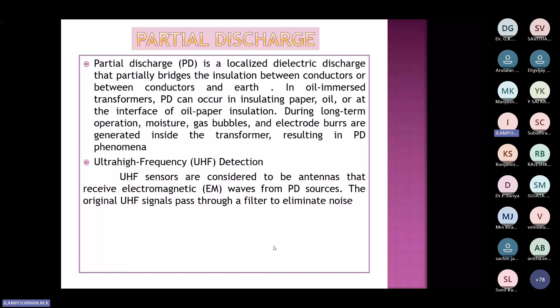If you have only one source of partial discharge, no problem, you can detect it perfectly. But God does not manufacture like that, you have multiple sources of partial discharge. So when you put an antenna, you will get a lot of garbage.